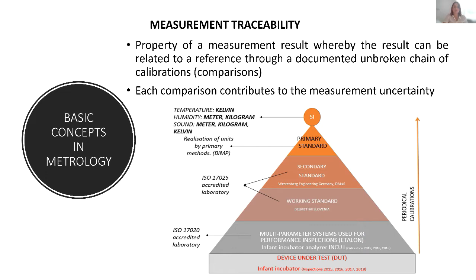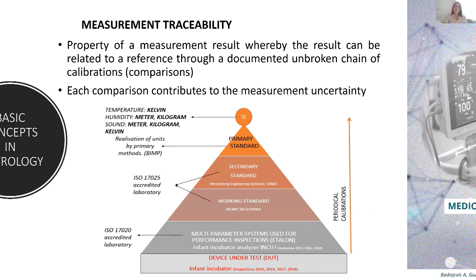For those measurements, we are using calibrated etalons of temperature and relative humidity. In order to build the reliability of a measurement, we calibrated our etalon by a working standard, which has greater accuracy. The working standard has been calibrated towards a secondary standard, again with a stated accuracy and uncertainty, and the secondary standard was calibrated to a primary standard. So basically, traceability is a known path with stated accuracies or uncertainties, which from the definition of the SI unit can be linked to the measurement of temperature and relative humidity performed in an infant incubator.